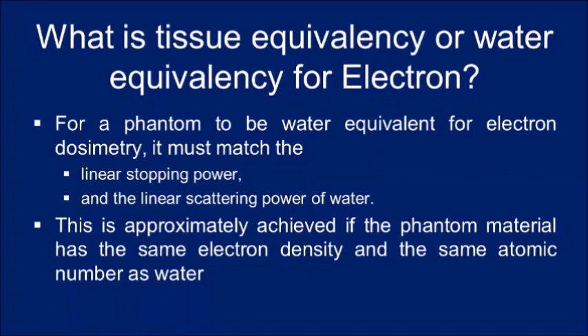For a phantom to be water equivalent for electron dosimetry, it should have the same linear stopping power and linear scattering power as water. This is approximately achieved if the phantom material has the same electron density and atomic number as water. If a material matches these properties, it can be used as a phantom for electron beam measurement.